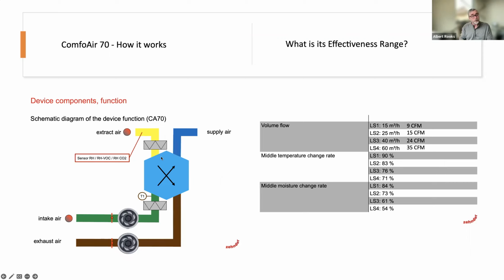This is a really, really good retrofit because we don't need to connect any ducting. We could just do it kind of room by room. And on the right-hand side, we'll just take a quick look at this. Low speed, so those are speeds. The thing's made in Germany, so they start naturally with cubic meters per hour instead of our CFM, but it's got a flow range of 9 to 35 CFM. So it's a small unit, but it's 85% effective. And in these small spaces, you don't need a lot of air. You just put a few of these on the building, and you get the flows that you want, and you try to deliver the conditions that you want.